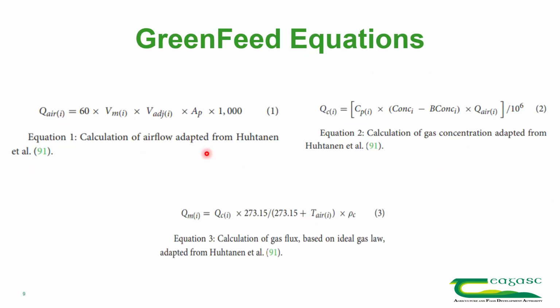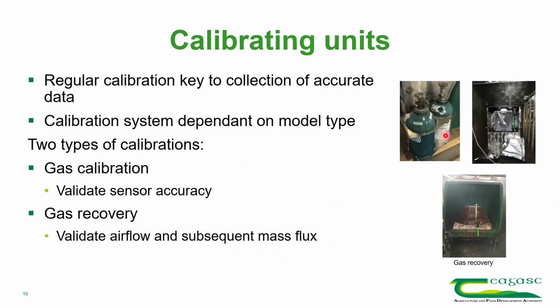So the first two equations, as I said, are airflow and gas concentrations. When you get your Green Feed system, you'll be doing quite regular calibrations with those systems, and these calibrations are key to accurately measuring methane emissions from these animals. Different calibration systems are in place - there's manual and auto calibrations, and they very much depend on the different model that you have with the system.